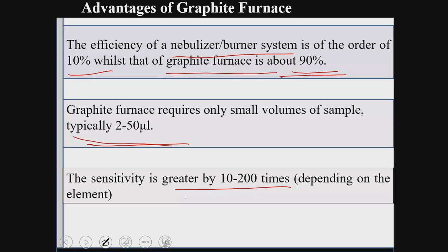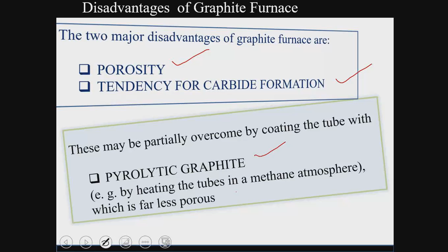Still, there are two disadvantages of the graphite furnace. One is its porosity, another is its tendency for carbide formation. These shortcomings may partially be overcome by coating the tube with pyrolytic graphite. This pyrolytic graphite can be prepared by heating the tube in a methane atmosphere.